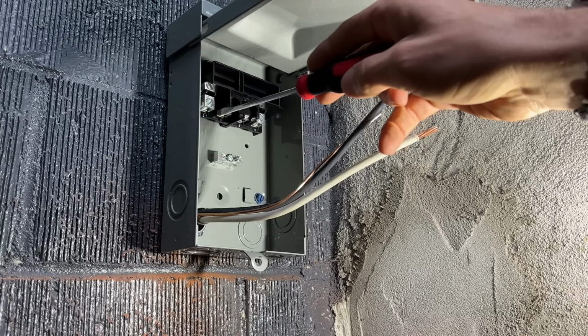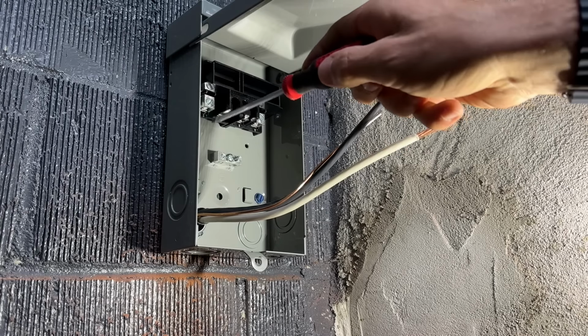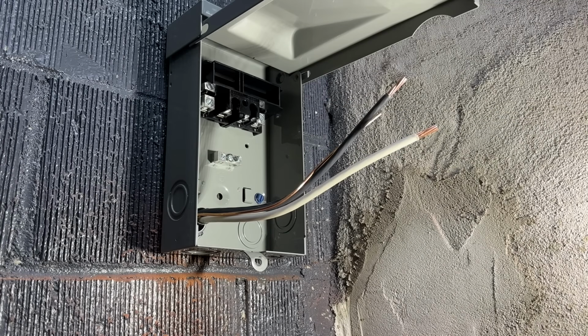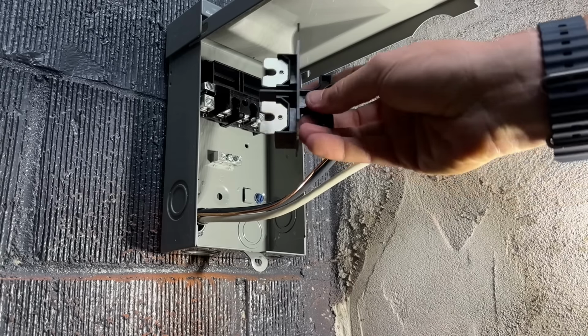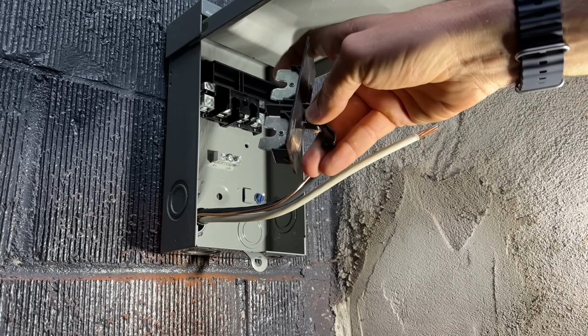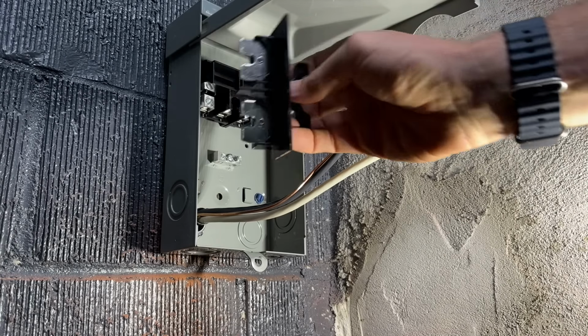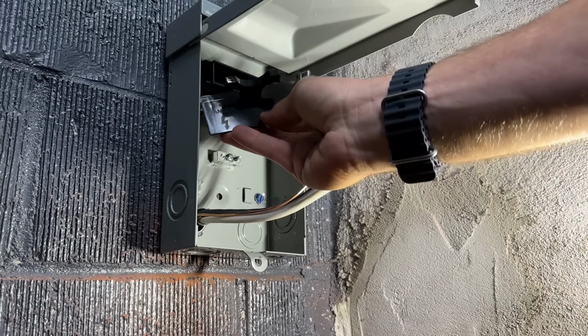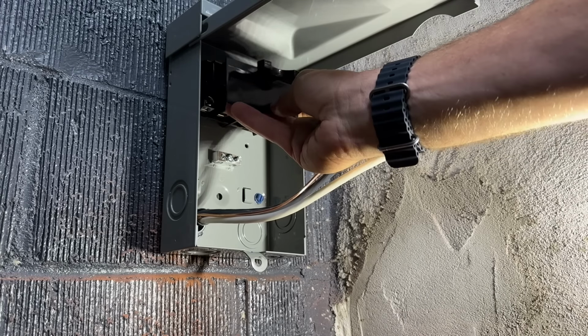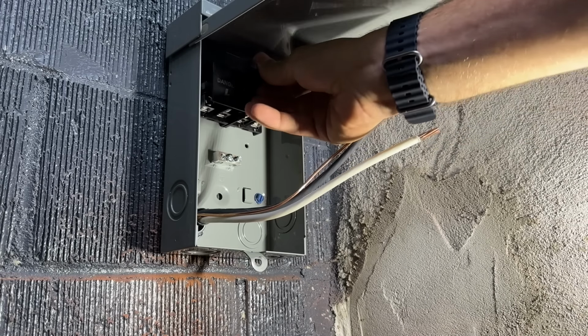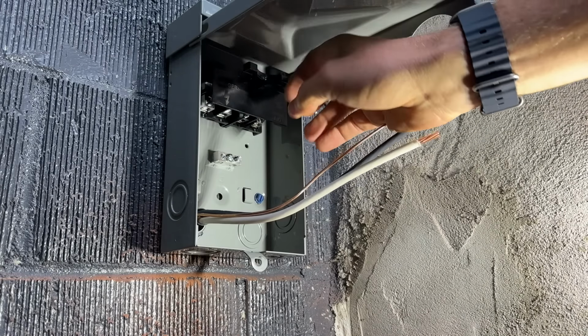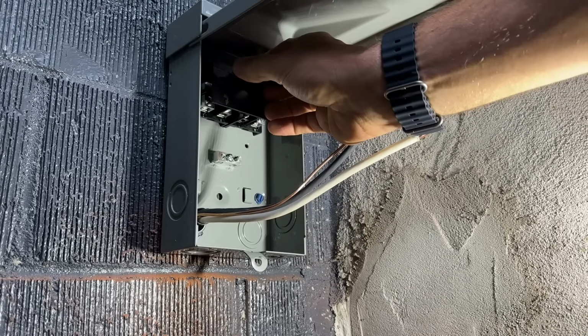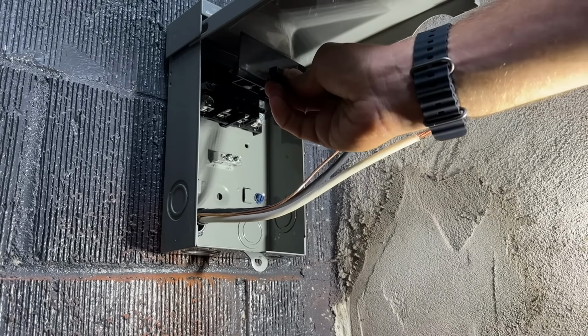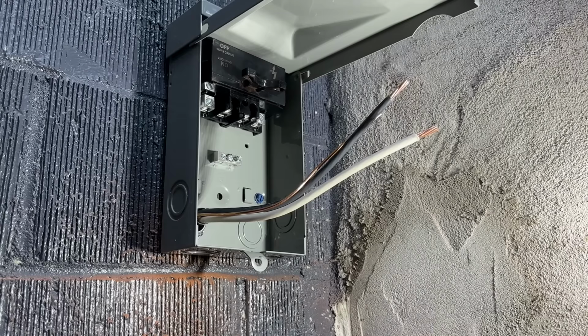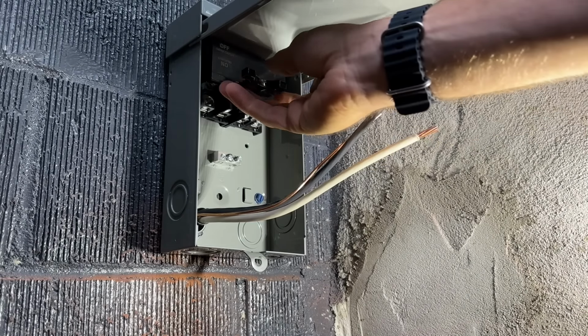And then the load, that going to the AC unit, will go ahead and go to the outside. That is how these disconnects work, right? It makes continuity between the line and the load. And in this down position, you can read on. That is when continuity is made. So you press that in, that's gonna connect it up, your unit's gonna be on. And then when you need to service it, you just pull it out, and you can flip it upside down where it's not making continuity, but you're able to store this in here so you don't lose it.